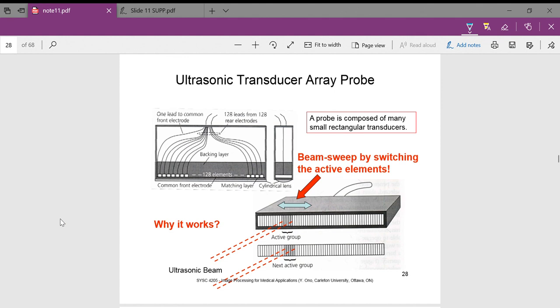Each element can be pulsed independently. By varying the timing — for instance, by making the pulse from each transducer progressively delayed going up the line — a pattern of constructive interference is set up that results in radiating a quasi-plane ultrasonic beam at a set angle depending on the progressive time delay. By changing the progressive time delay, the beam can be steered electronically. It can be swept almost like a searchlight through the tissue, and data from multiple beams are combined to make a visual image showing a slice through the object.